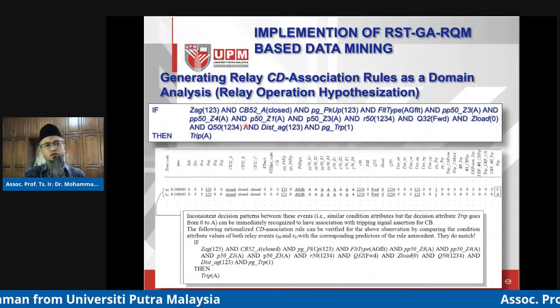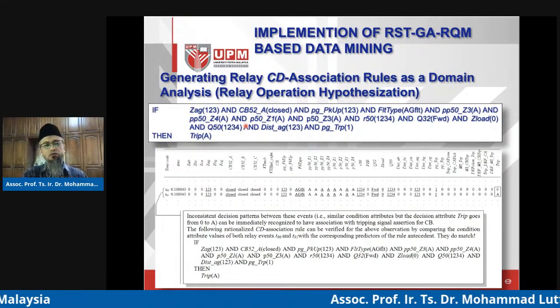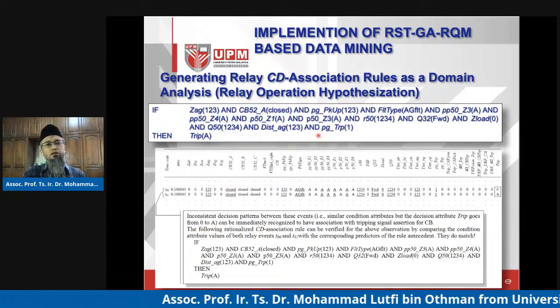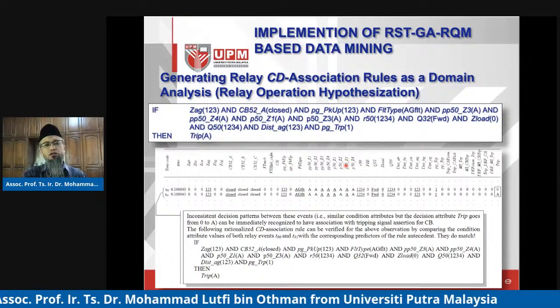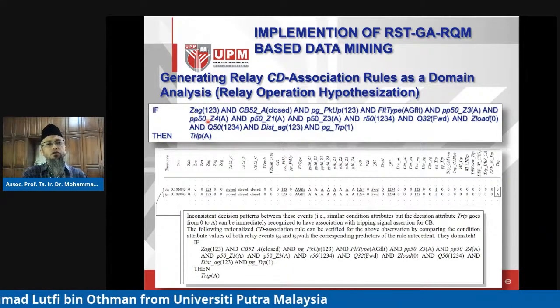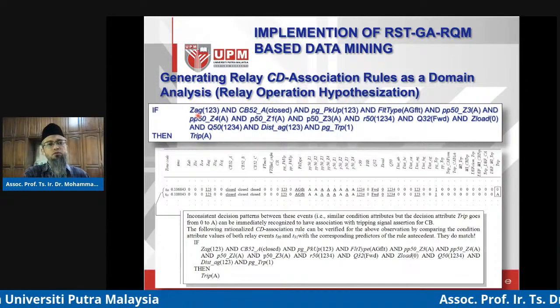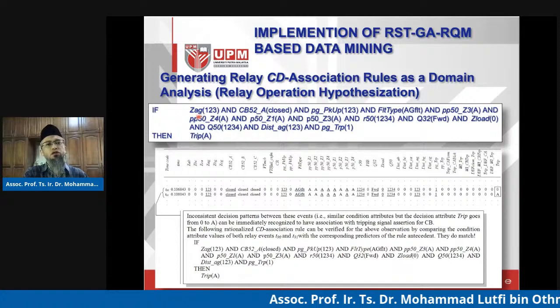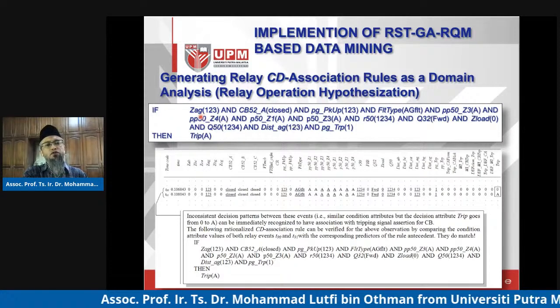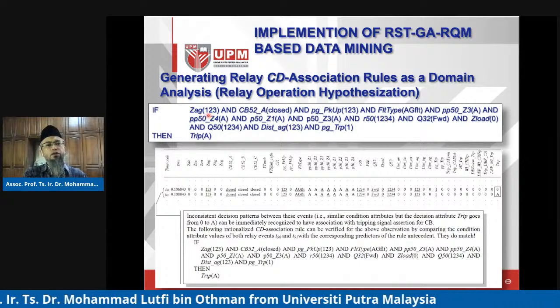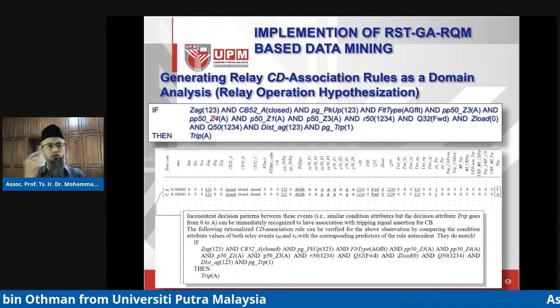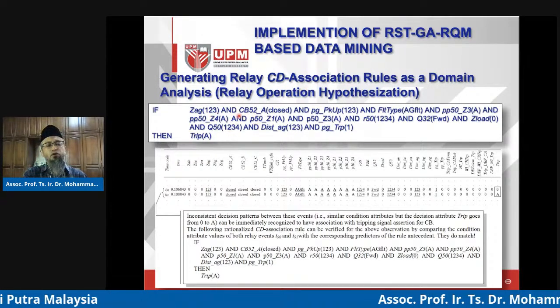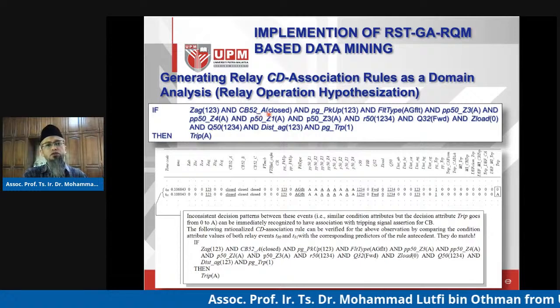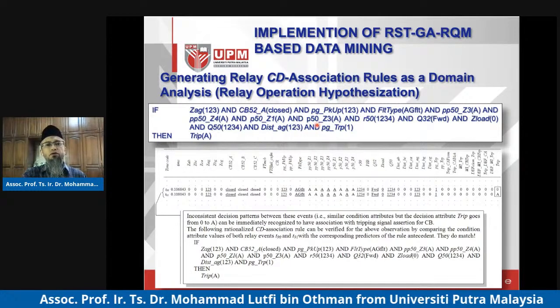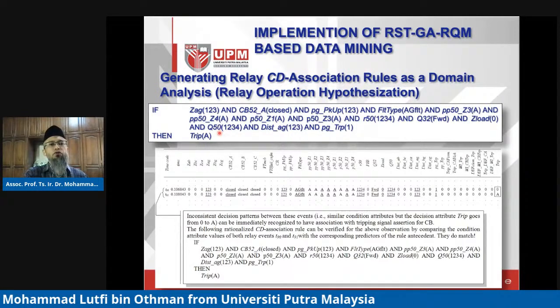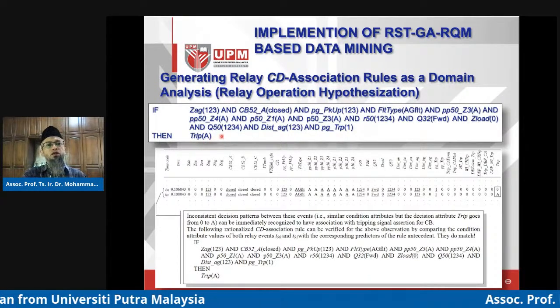This rule is being tested over the A-to-ground fault at zone number 1. These are the original 46 attributes. One of the 7 reduced attributes is the functional unit called detection unit of phase-to-ground fault, given a value of zone 1 — meaning the impedance trajectory has to go through zone 3, then 2, then finally zone 1. At that point when the fault occurs, the breaker is still closed, and the internal functioning units of the relay finally give out tripping signals. These are the conditions, and this is the decision.